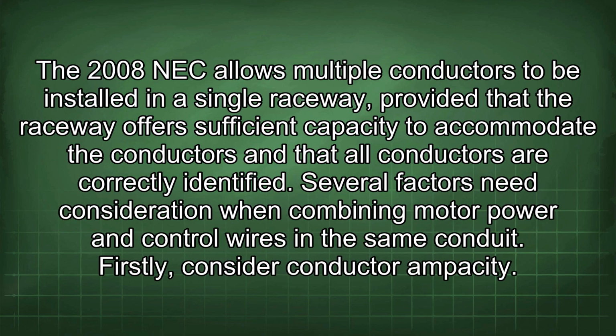The 2008 NEC allows multiple conductors to be installed in a single raceway, provided that the raceway offers sufficient capacity to accommodate the conductors and that all conductors are correctly identified. Several factors need consideration when combining motor power and control wires in the same conduit.